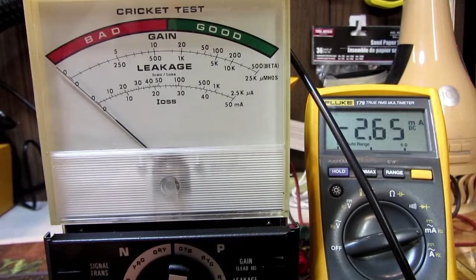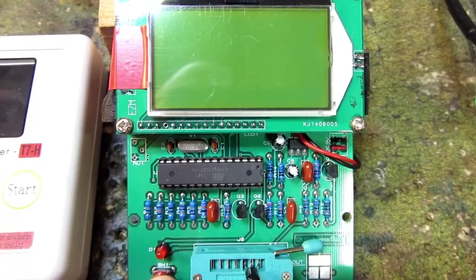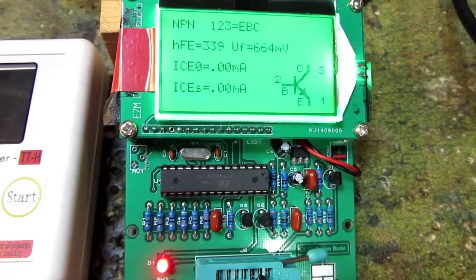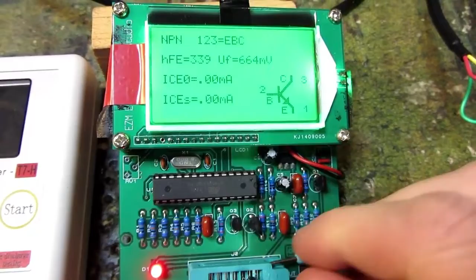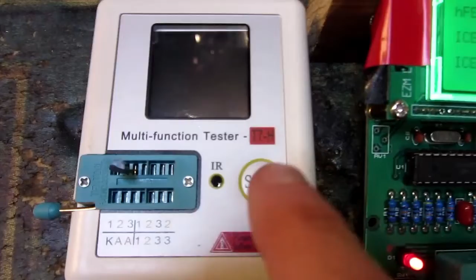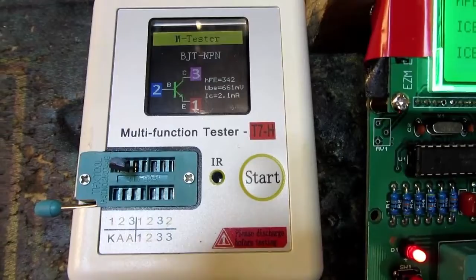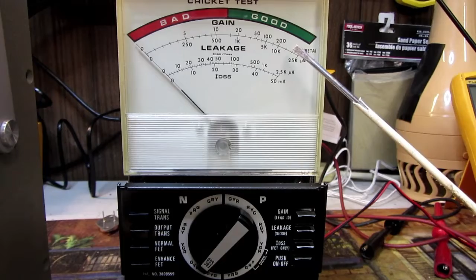Okay, the next step will be to calibrate the beta. This transistor, a 2N3904, generally tests around 350 beta. Okay, it's testing 339. So we'll test it on the other machine. It's testing 342 here. So it's approximately 340 beta. On the beta scale here, the second line over, above the 200, is 300. The next line is 400. Okay, that looks to be just a hair below the halfway mark from my vantage point between the 300 and 400, so we're going to call that accurate.